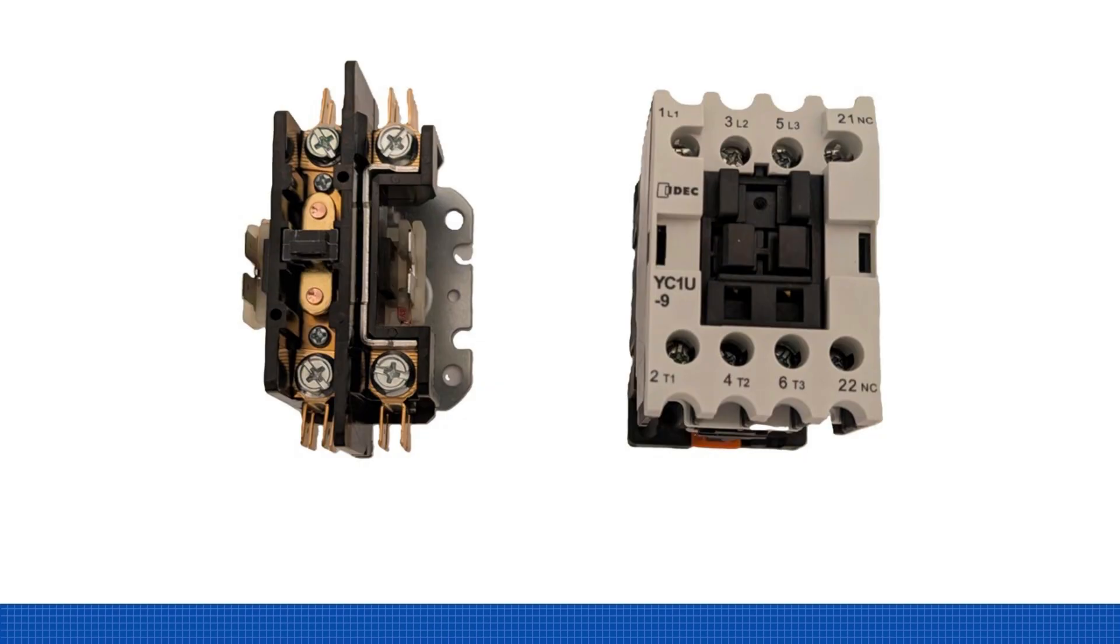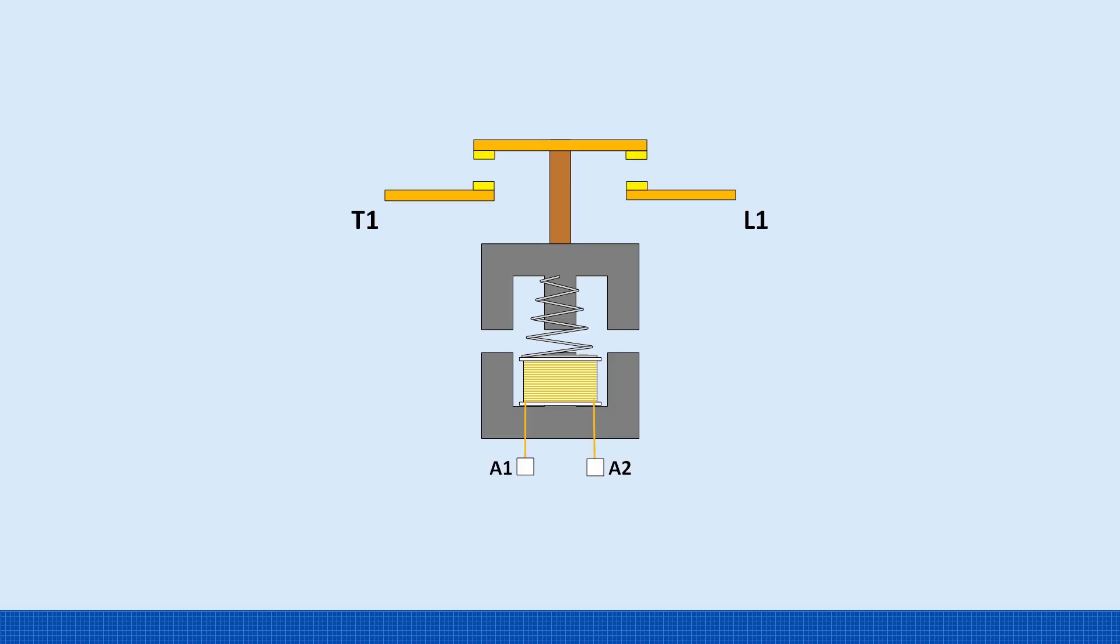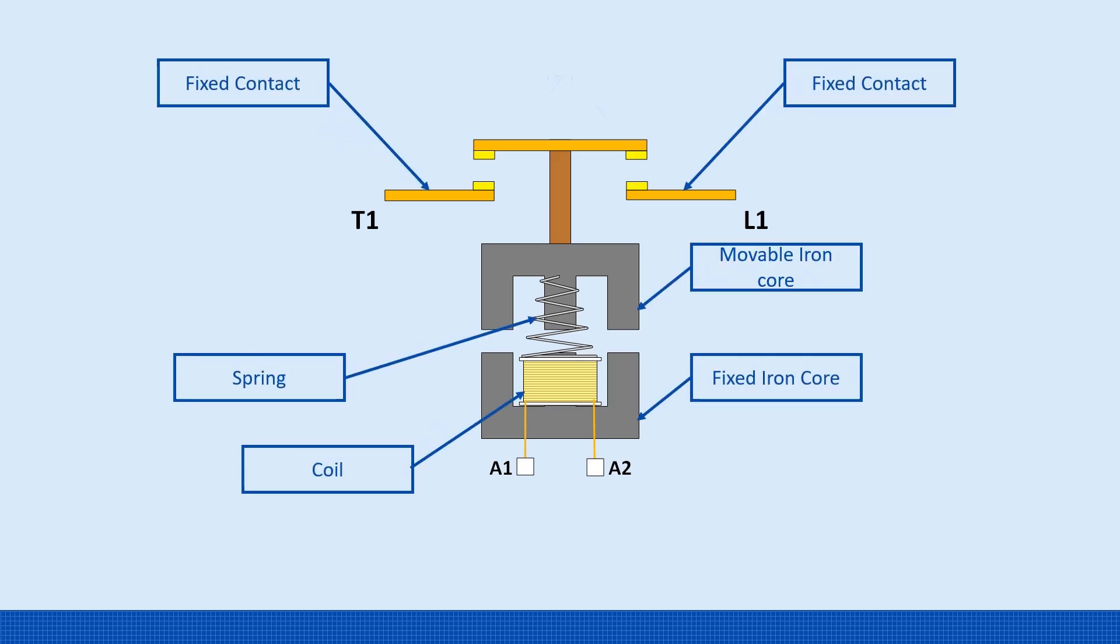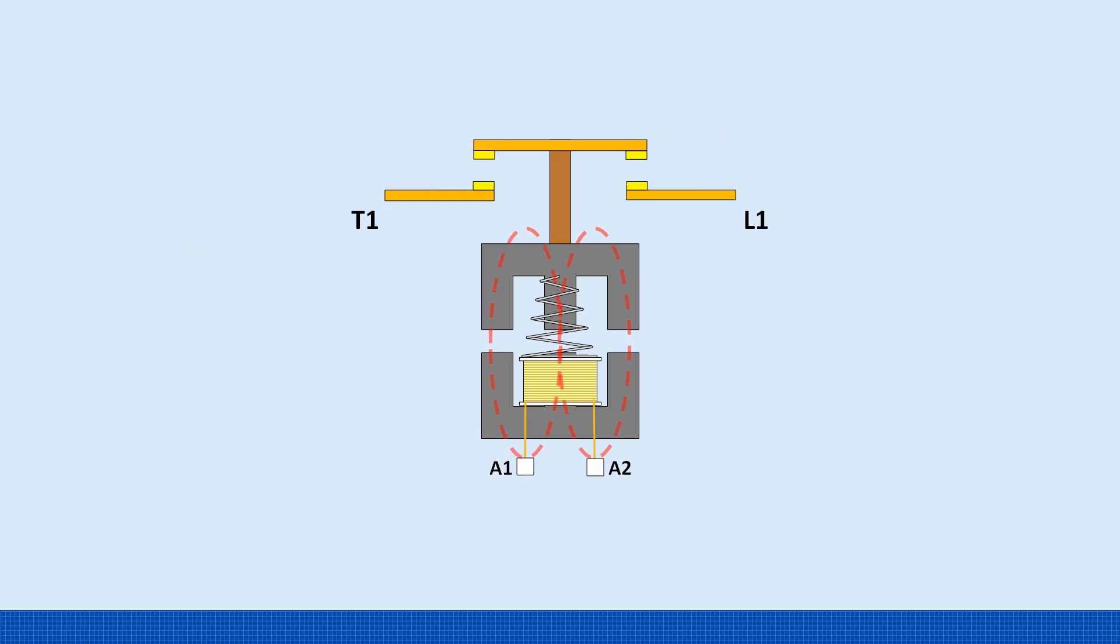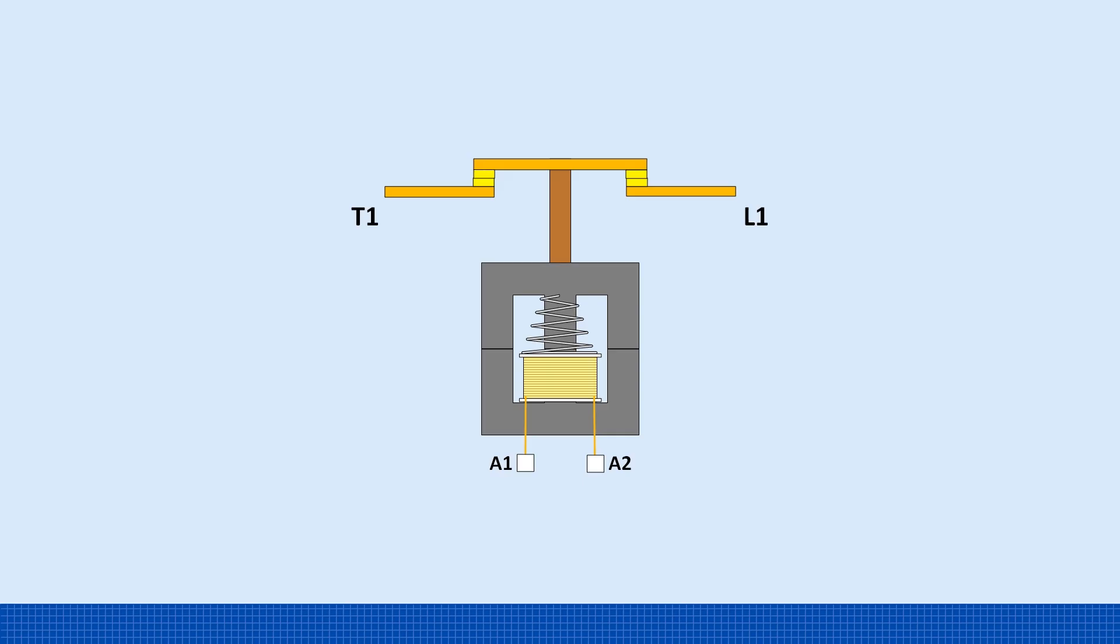So how does a contactor work? A contactor is made up of a few key parts: a fixed iron core, a coil, a movable iron core, a return spring, fixed contacts, and movable contacts. The movable contacts are connected to the movable iron core using a non-metallic arm, so there's electrical isolation between the coil and the power contacts. When power is applied to the coil, it generates a magnetic field. This field magnetizes the fixed iron core, which pulls the movable iron core downward. As the movable core moves, it pulls the arm with it, closing the contacts.